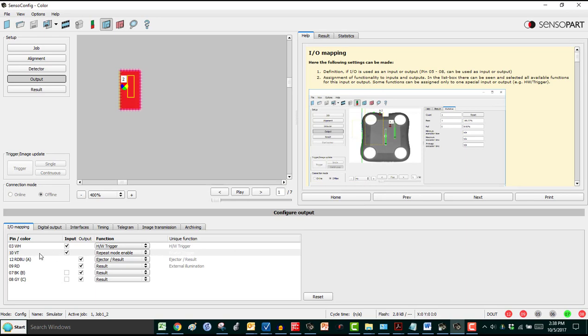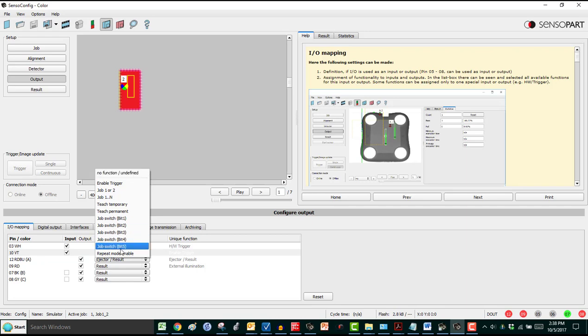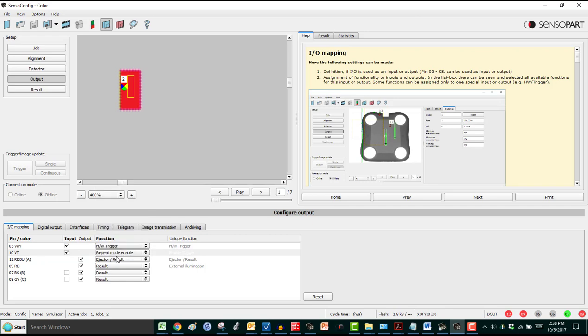The second thing we need to talk about is we've got Violet configured for repeat mode enabled. Out of the box, it's no function. We need to put it to repeat mode enabled, and this is where we'll land the output of our photo eye.